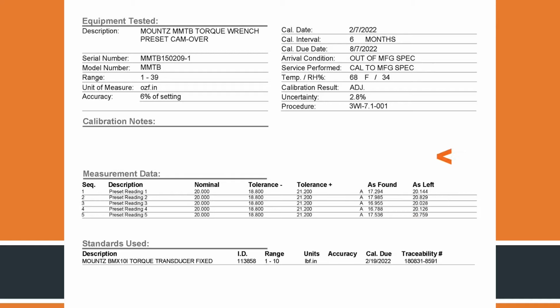But this gives us what we see here as the service performed. It was calibrated back to the manufacturer specification, and then we have our calibration readings as left, and then we have which model or sensor the unit was calibrated on, and then we have the traceability information here for that analyzer. So if we did want to go and trace this back to the wheels and weights that were used, we could do that with this. But that's typically what you'll see on a torque calibration certificate.